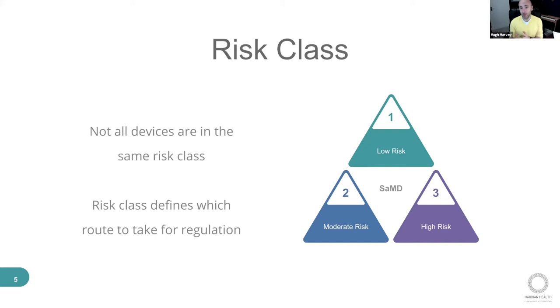Your risk is identified by your intended use, so what you're claiming it to do, but also the highest possible harm that could occur to an individual patient as a result of someone using your device. In general, software is at least class two, but can be class three. It tends not to be class one unless it's staying well away from decision support or diagnosis. Low risk devices are things that just kind of store and process information and maybe present them in a presentation layer rather than actually do anything active or decision-making with the data.